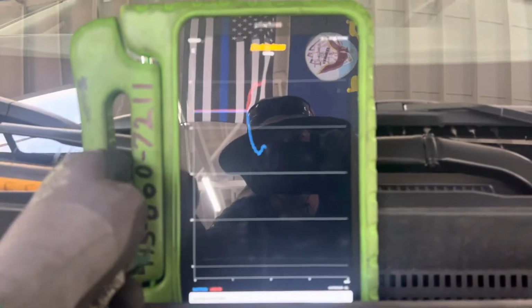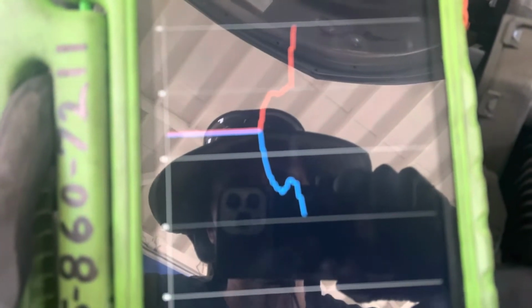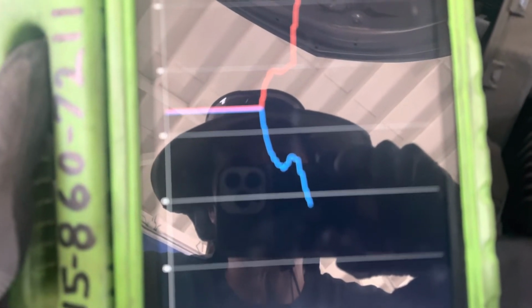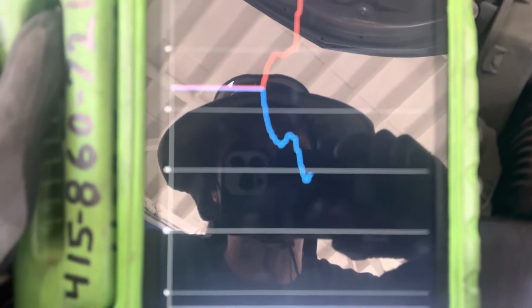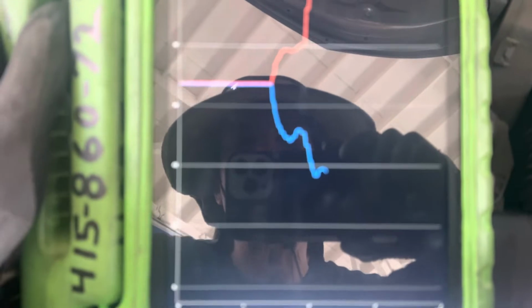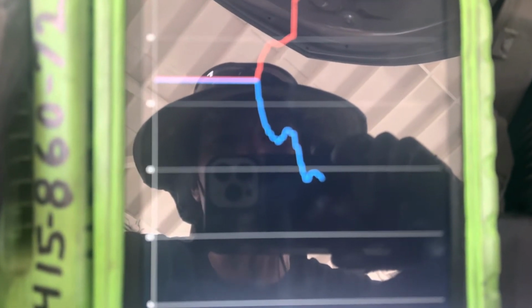And can you see where it took off? It just went balls to the walls and started cooling, so it's cranking. And it looks like it just stepped up to step number 2. So you could see where it turned on and it went to a certain level, a certain speed, RPM. And then it kind of settled out for probably 10, 15 seconds. And then it hit another level, you can see it here, and then it went faster. Let's see if it's going to pull some more.